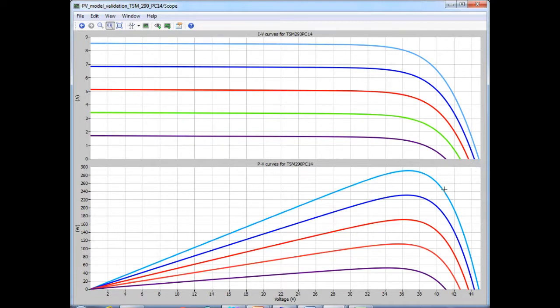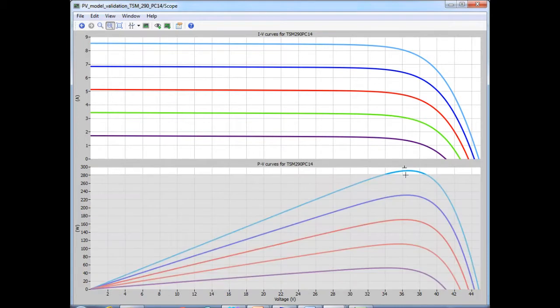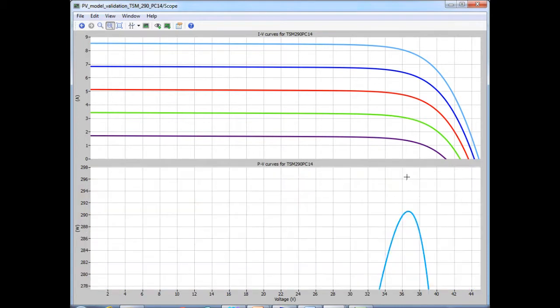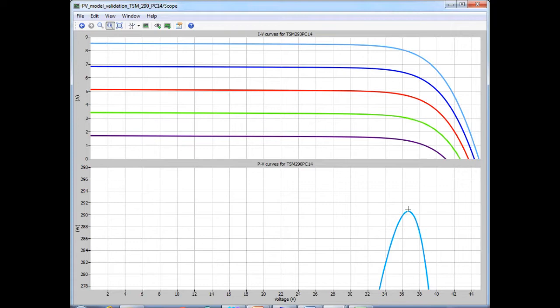Let's also zoom in in the PV curve exactly near the peak power point. You can see that the peak value, so this line here is 290 watts, so this is roughly 290.7 or so. The expected PMP, maximum power from the datasheet, was 290.2, so we are very close to that.